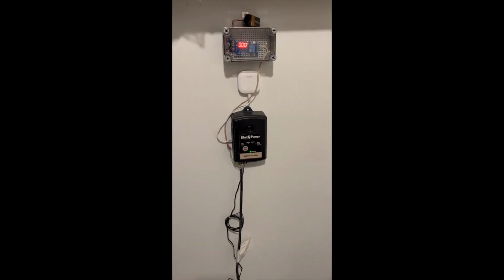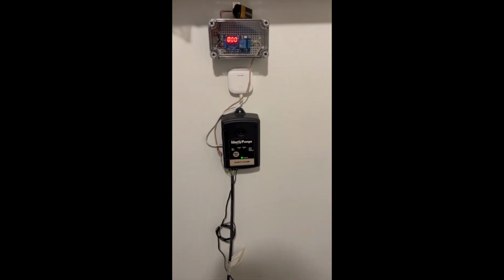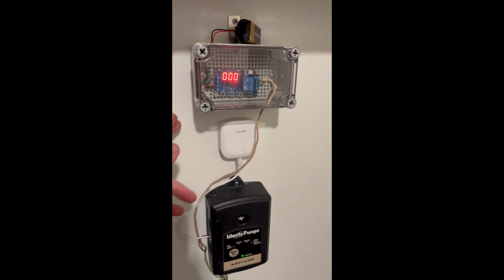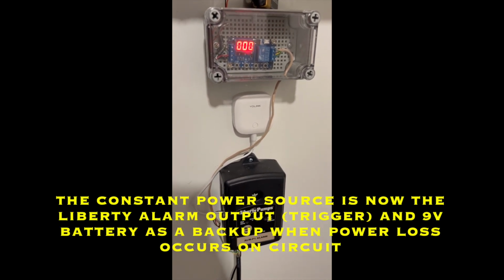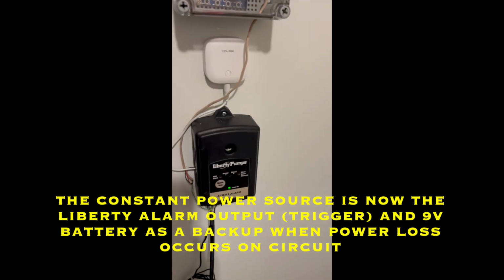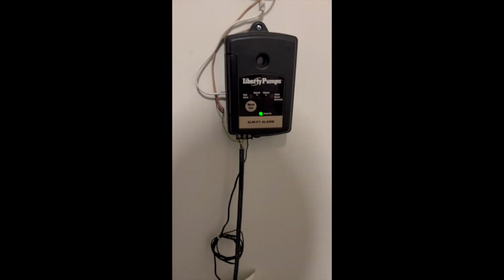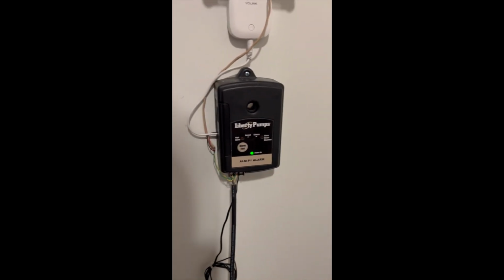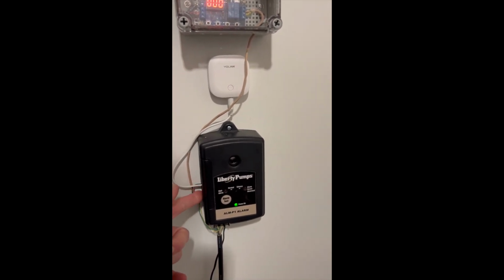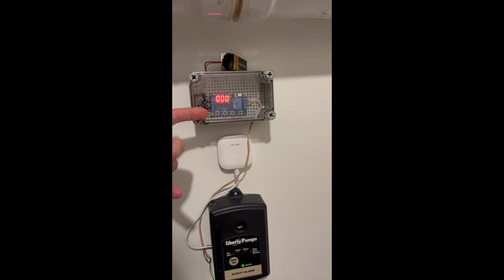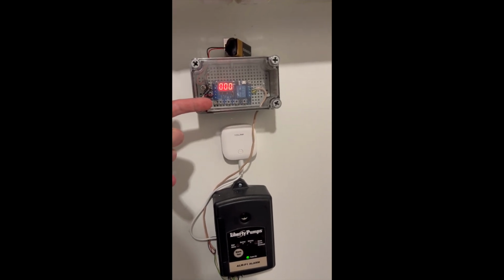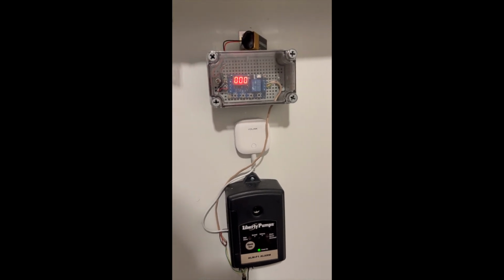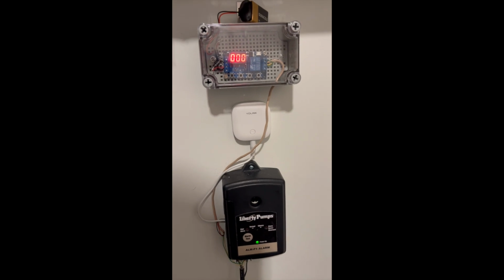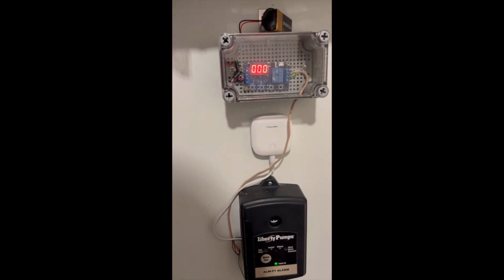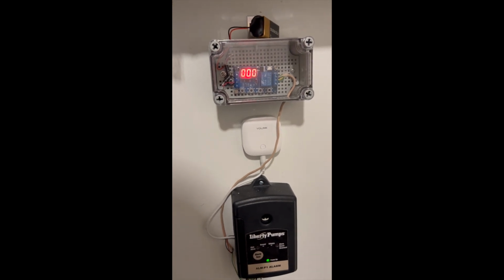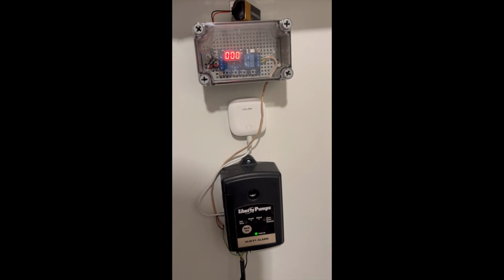So here we are mounted back in the pump room with the modifications made. You see the 9-volt battery attached, and the absence of a constant power source. Now we have it hooked up exactly the same way as before to the pump alarm. The relay contacts go to the alarm contacts. The power output here feeds both the trigger and constant power source, and the 9-volt battery feeds the constant power source as well, each going through the diodes so as not to feed back to each other on the positive side. Everything seems to work well. So I cleaned up the installation a little bit.